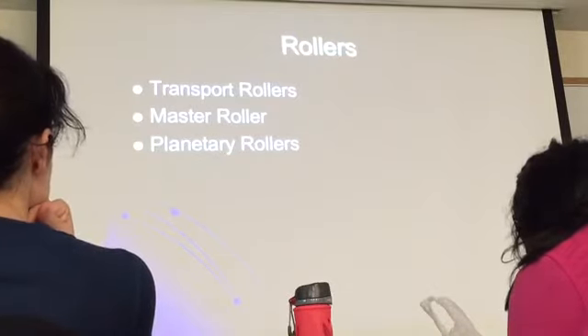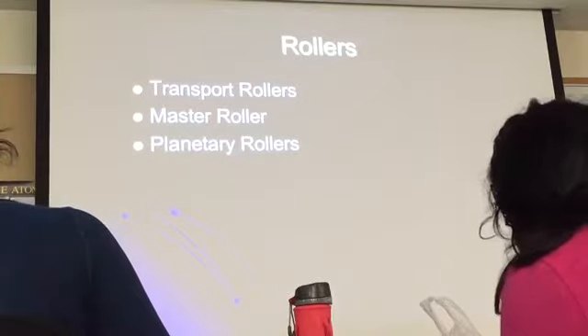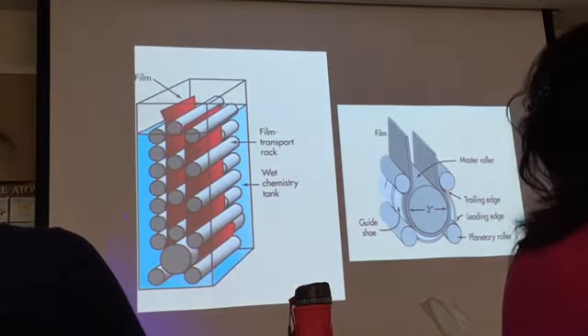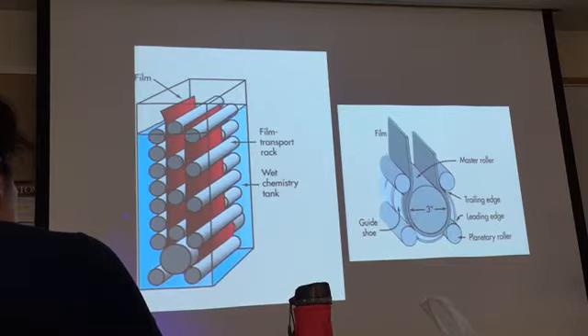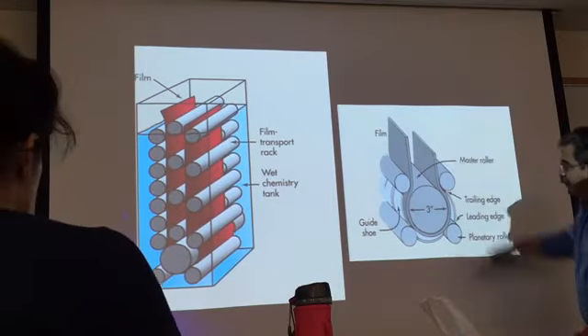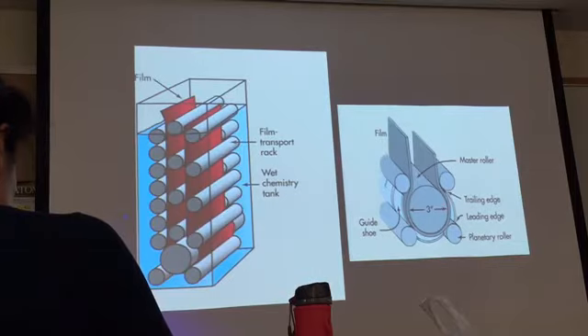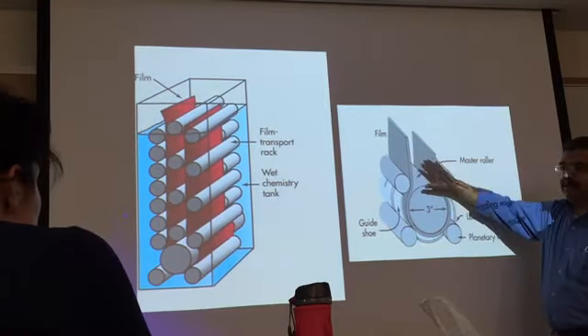The planetary rollers surround the master roller and are there to also help the film turn. These are the transport rollers sitting opposite to each other. You have the master roller here — a three-inch roller — and then a set of four planetary rollers surrounding it. Also at the bottom is the guide shoe, which is a curved, concave aluminum plate to help the film turn. All of this is called the turnaround assembly.